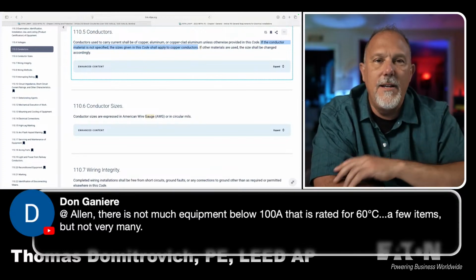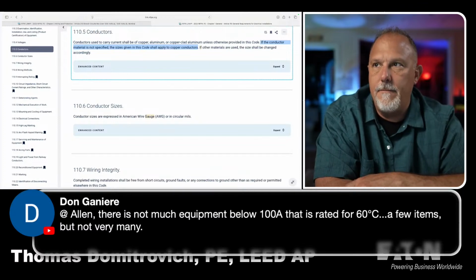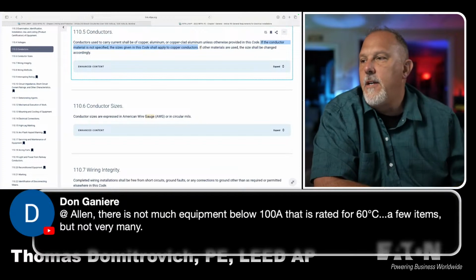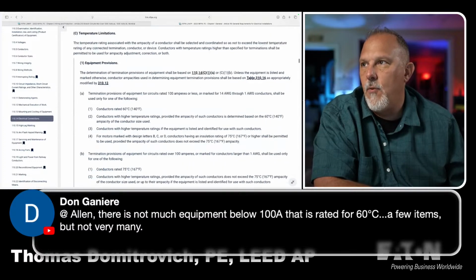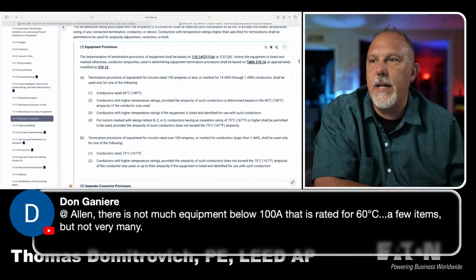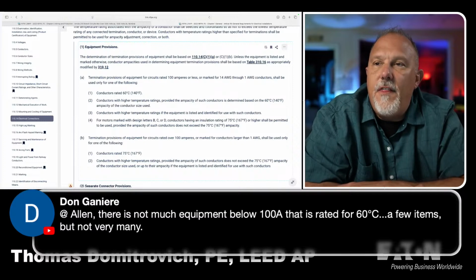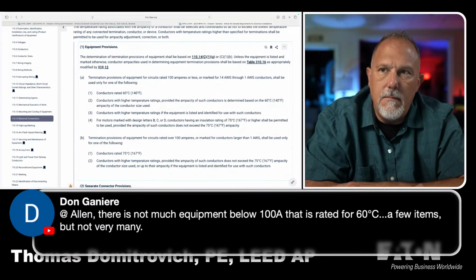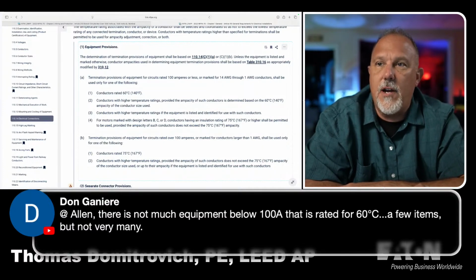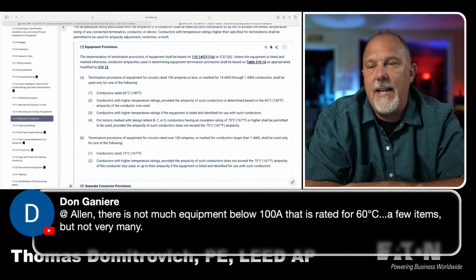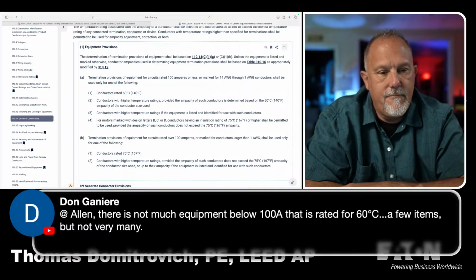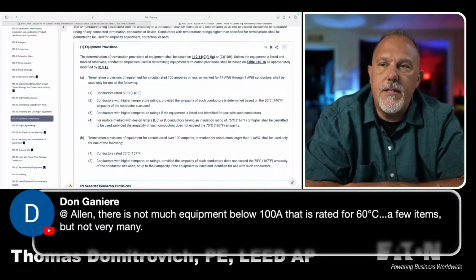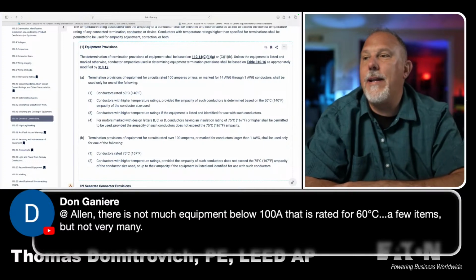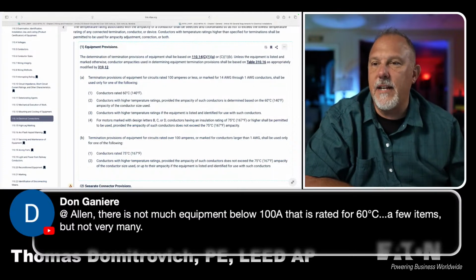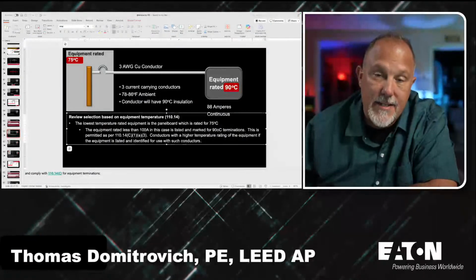Now, I know I have this caveat: if other materials are used, the size shall be changed accordingly. So if I come down here to 110.14, this says termination provisions of equipment for circuits rated 100 amps or less, or marked 14 gauge through 1, that's copper only. Would you agree? So does that mean that this doesn't apply if I have copper-clad or an aluminum conductor? It does say I have to adjust it appropriately. I'm just a little bothered with this one. So in any case, conductors with higher temperature ratings, if the equipment is listed and identified for use with the conductors. That's what I'm going by. That's my story, and I'm sticking to it.